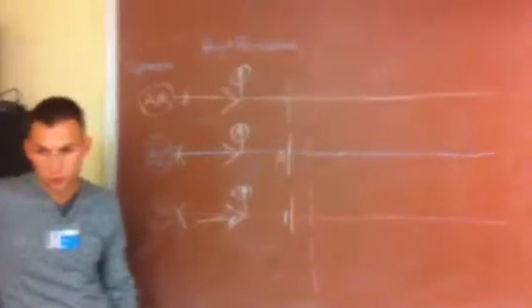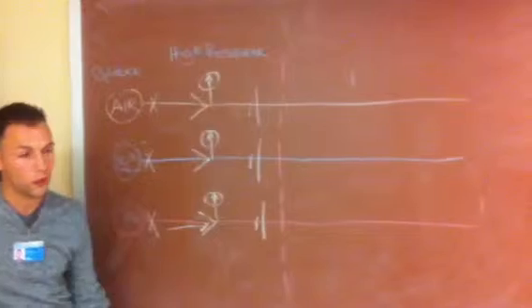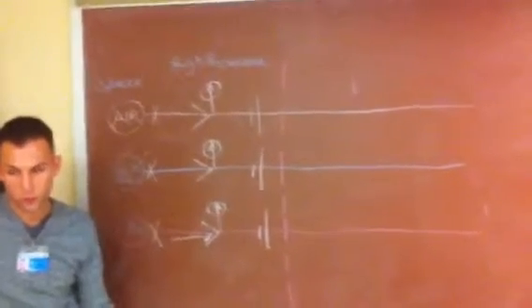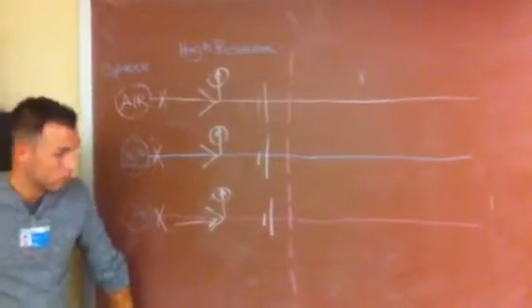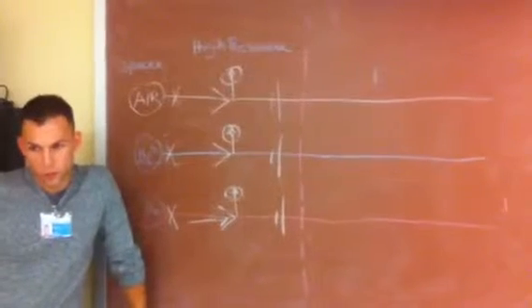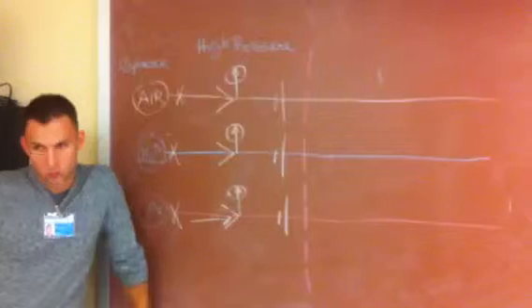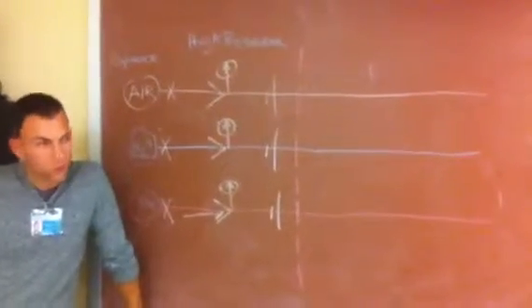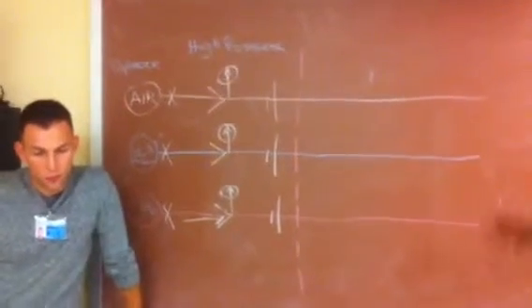All right, according to this, it's a clinical moment, right? After the cylinder has been attached to the yoke, the valve should be closed unless it is to be the primary gas supply for the machine. If the pipeline is the primary supply and the valve remains open, fluctuation in gas pressure in the machine could allow some or all of the gas to exit the cylinder. Right. That's why when you attach it, it should be closed if the pipeline is fully functioning. Because the cylinder is only the secondary supply of oxygen when you have the pipeline.